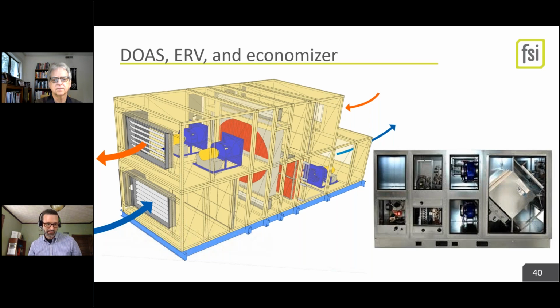On the DOAS side, there's also an economizer function on the space conditioning side to discuss. So you get true free cooling. But there are a handful of hours a year, maybe 50, where it makes a lot of sense to bypass that wheel. You're actually hurting yourself energy-wise instead of helping yourself. But again, it's a small handful of hours a year.